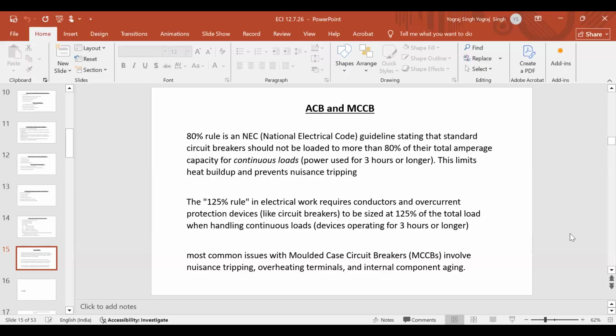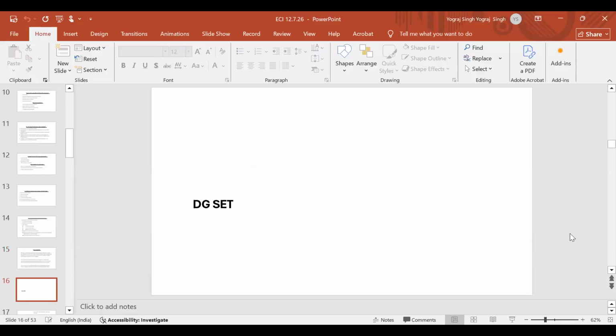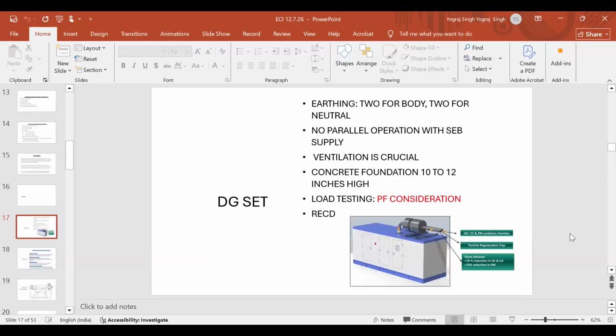MCCBs: nuisance tripping, overheating terminals, and internal component aging are the problems with MCCBs. Now I'll come to the DG set. For the DG set, I had shown you a figure of earthing. So earthing is important for any power system, whether it is a transformer or a DG set.